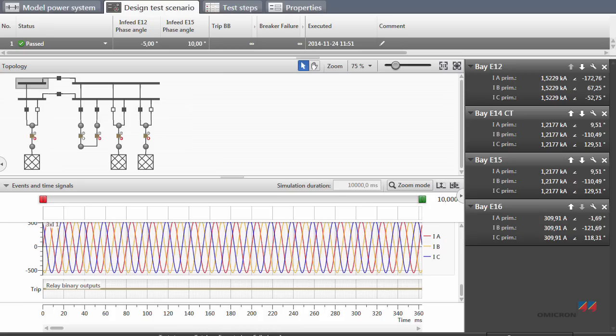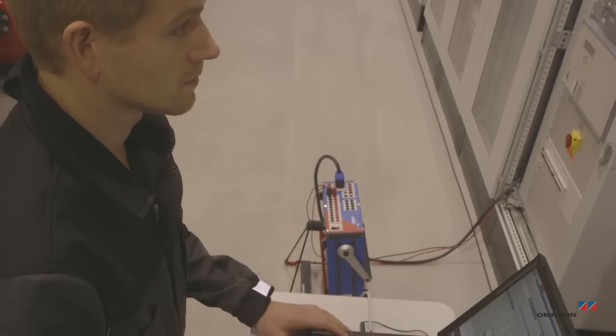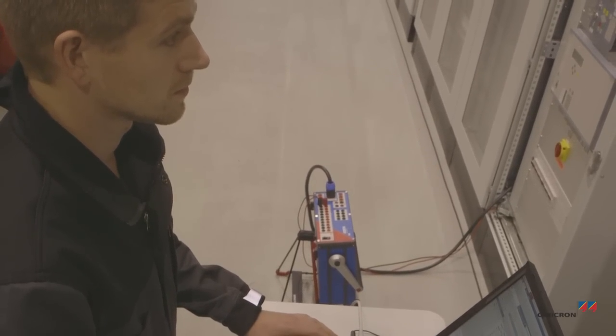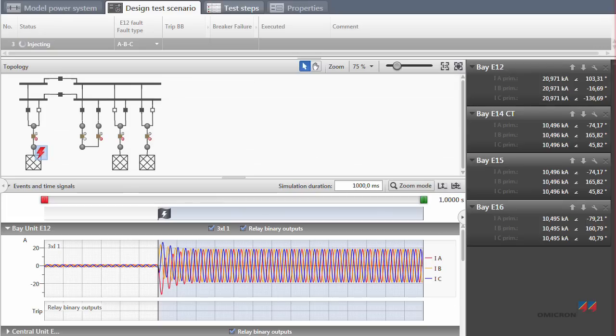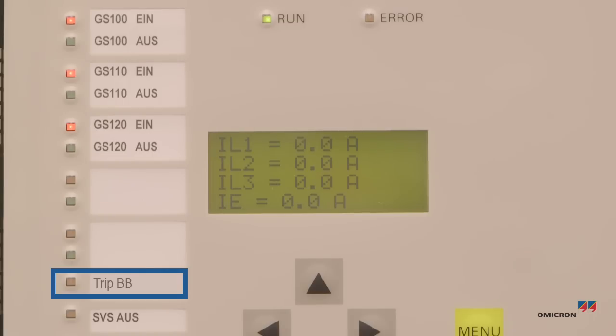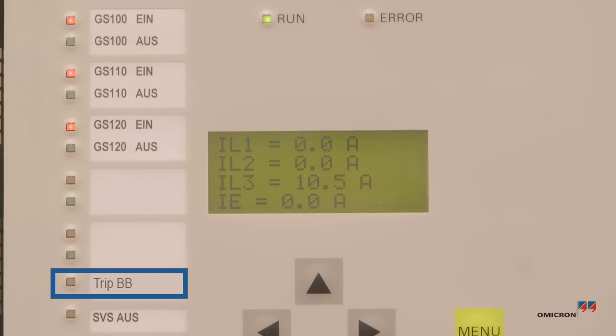The protection has passed this test. Now Florian simulates a fault. Although the fault has taken place in one of the bays, it remained outside of the protected area of the bus bar protection. None of the bays have tripped. The protection remains stable.